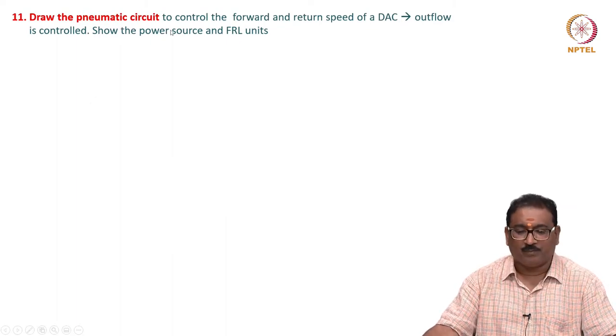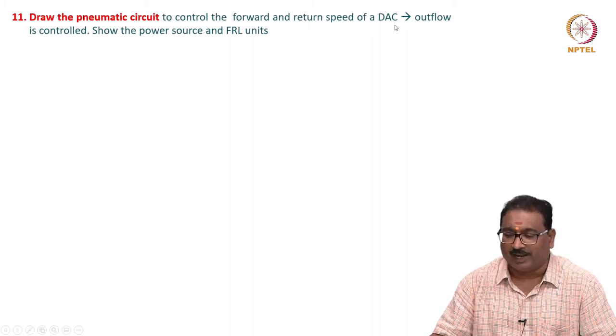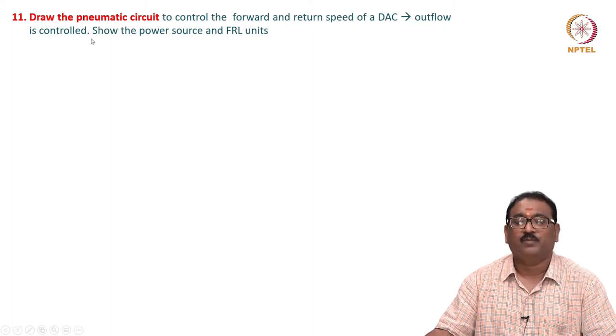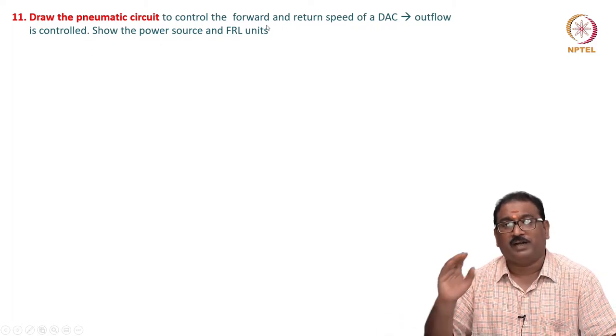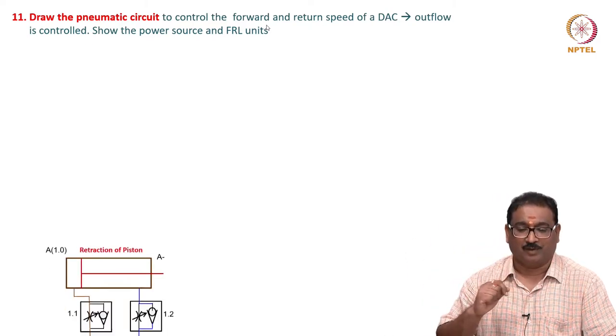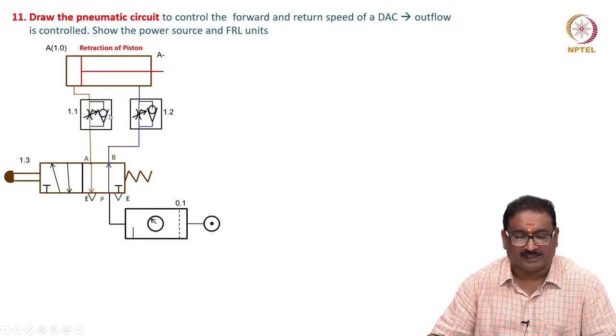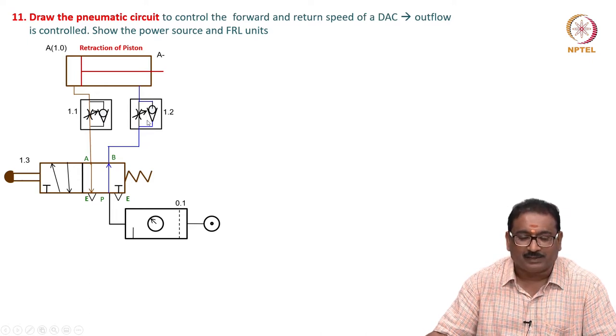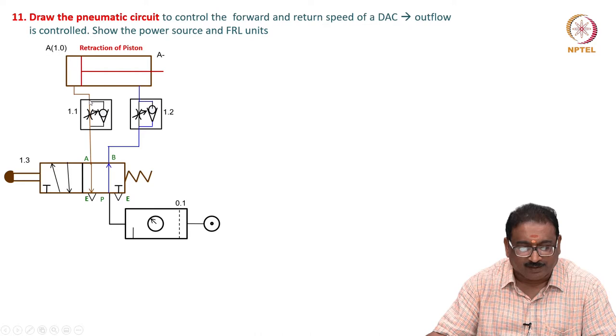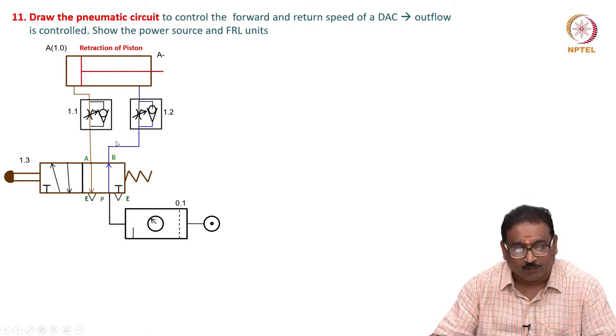Next: draw the pneumatic circuit to control the forward and return speed of a double-acting cylinder, where outflow is controlled. Show the power source and FRL unit. Both forward and return should be controlled but outflow is controlled. The position of the check valve matters. For retraction, the power source comes here - it bypasses through the check valve on the inlet side. Inlet is not controlled. On the outlet, when the piston pushes, the outlet cannot pass through the check valve - it passes through the metered orifice. Outflow is controlled, so it retracts very slowly even though full flow is coming in.